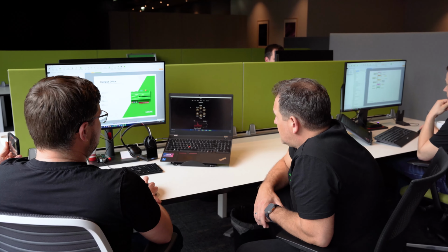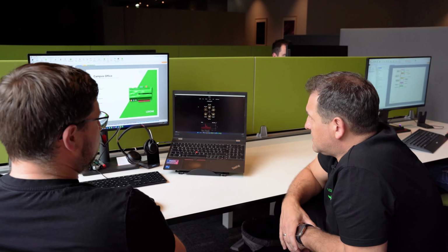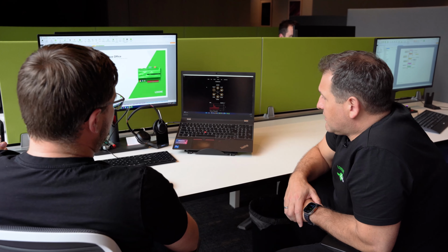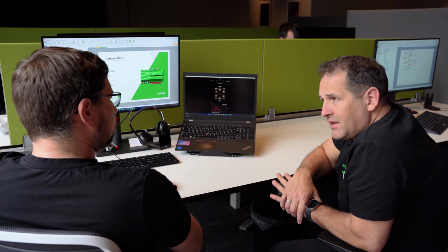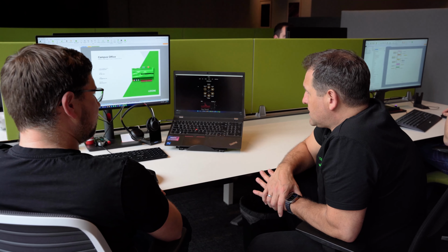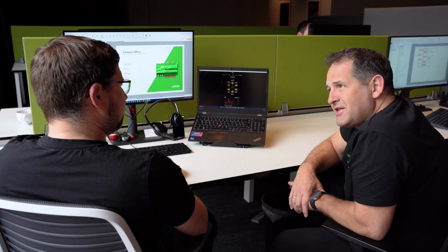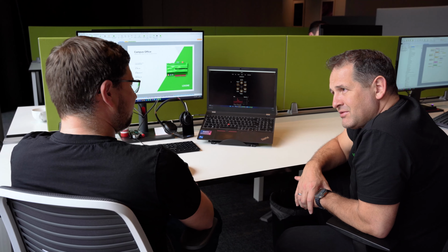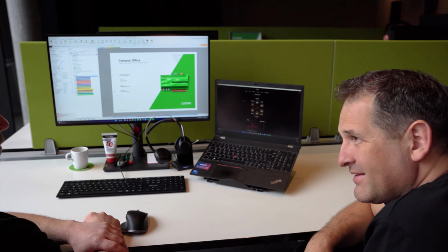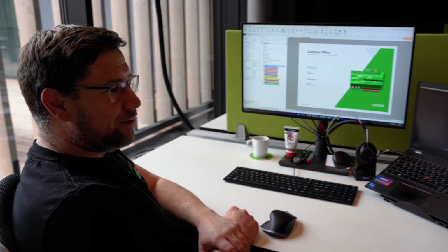Yes, we've had relatively large consumers. The rest is in the heating, where we were initially unsure as to exactly where the energy was flowing. So we looked into it and found there were a few valves which were not yet connected, and so we're always in the manual position, which was set to 100% on flow. So we closed them by hand, and this solved the mystery, getting rid of the energy leak.